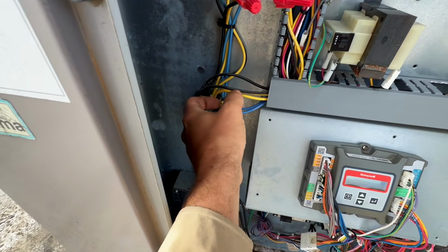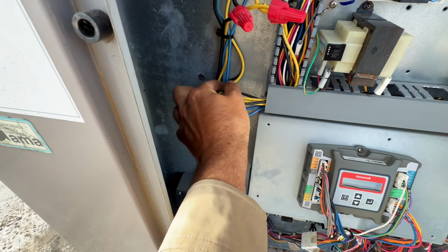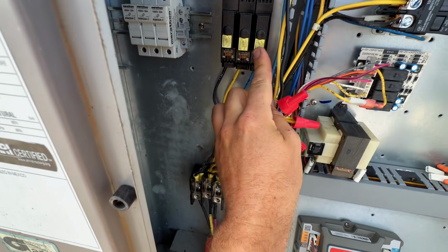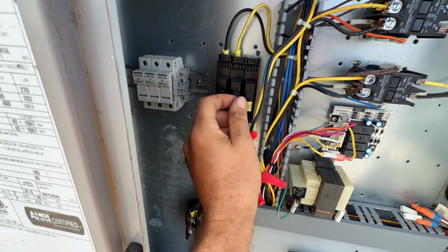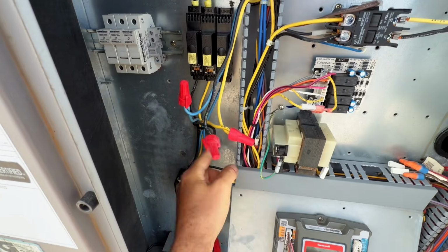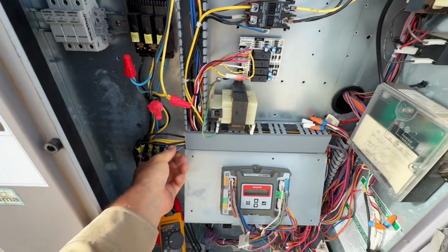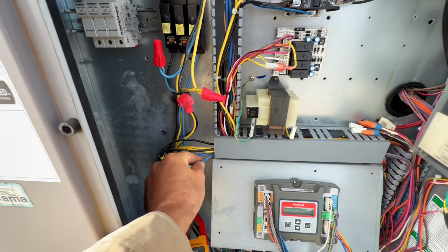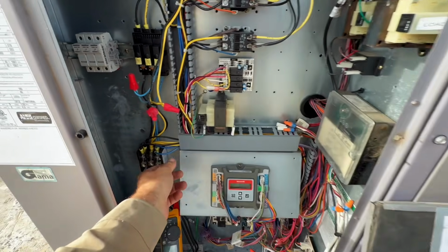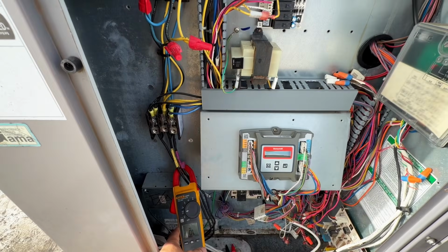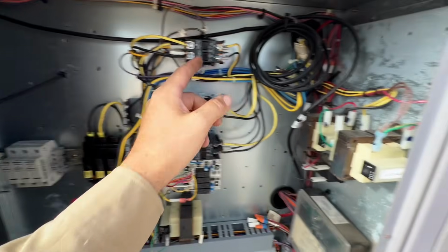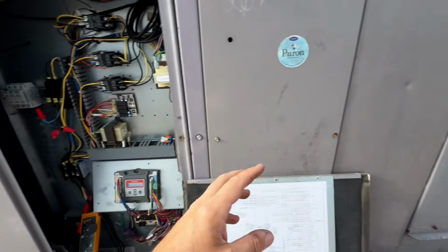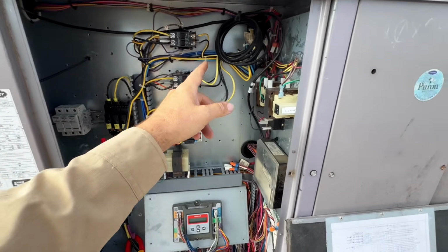But now here we have 4 blue wires, and we do have fuses here that were bypassed at some point. So we have 4 wires. Obviously you can go through, you can disconnect this, isolate which wire is the one that causes the connection to ground, and then trace that wire. You run through, you open all of your panels and you see where the wire goes.